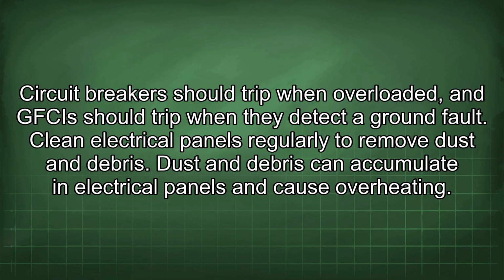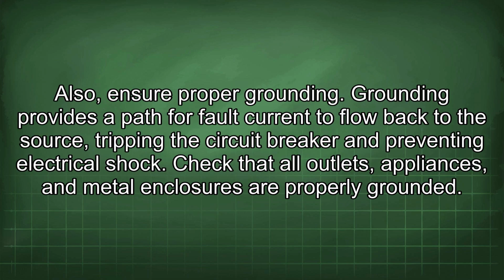Clean electrical panels regularly to remove dust and debris. Dust and debris can accumulate in electrical panels and cause overheating. Also, ensure proper grounding. Grounding provides a path for fault current to flow back to the source, tripping the circuit breaker and preventing electrical shock. Check that all outlets, appliances, and metal enclosures are properly grounded.